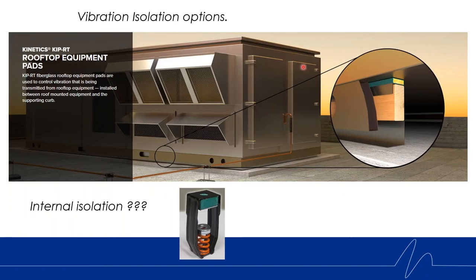One of the most simple solutions is to use an isolation pad. Often the spring rail or isolation spring rail is something that will get value-engineered out — it's the first thing to go when the budget gets tight on a project. But one of the cheapest solutions, a nice cheap insurance, is to put an isolation pad onto the curb. Here you can see a Kinetics fiberglass isolation pad sitting right on the factory curb, and then the unit sitting down on top of that isolation pad. This is not going to work as well as a spring, but it will offer some isolation to vibration from that unit for a lot less cost.